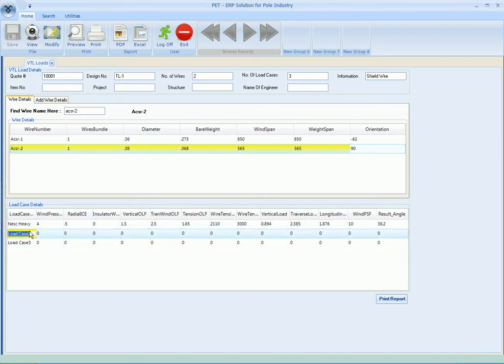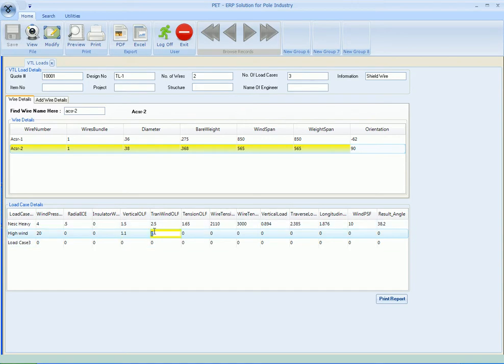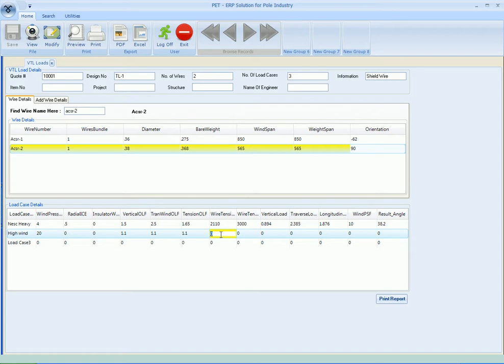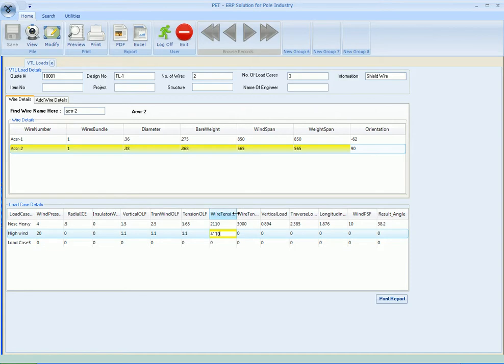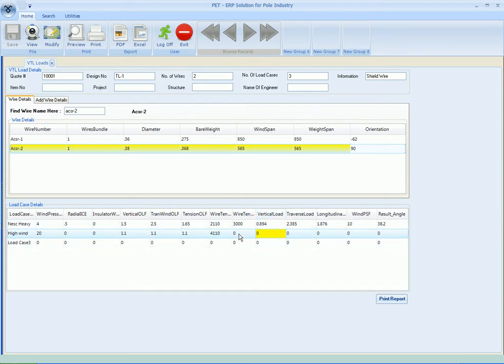And this is the longitudinal load 1.875. This is the wind PSF 10 and resultant angle is 38.2. The same way we'll do for load case number 2 - let's say it's high wind. The wind pressure this - let's say it's 20, radial ice 0, insulator weight 0. Vertical OLF let's say 1.1, 1.1 for the transverse wind OLF, tension OLF 1.1.